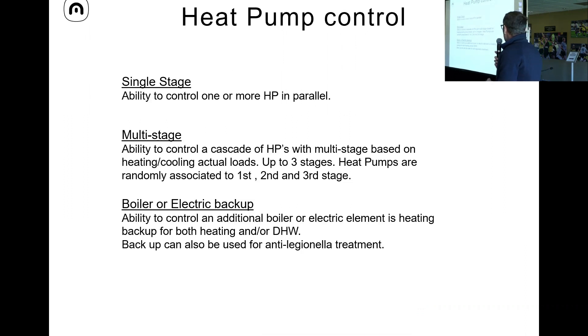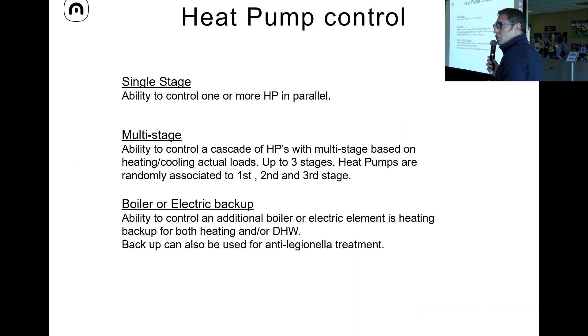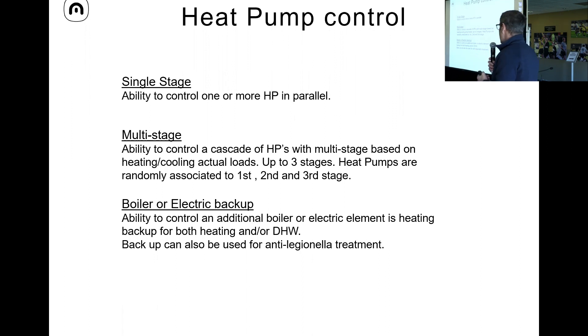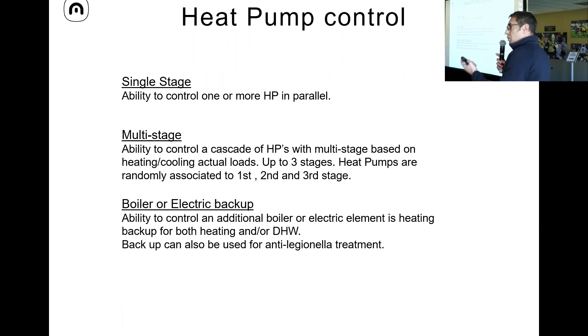We can control heat pumps in single stages, one or two heat pumps in parallel, or with a multi-stage strategy. For bigger residential houses, you can attach two or even three heat pumps and stage them — activating all three to reach the set point and then modulating down. We also reset the array of heat pumps so that each one can serve as first, second, or third stage, and you don't always have the same heat pump in the first stage.